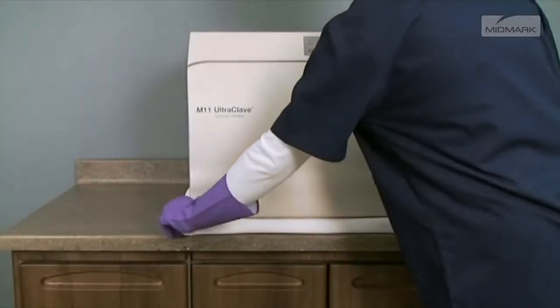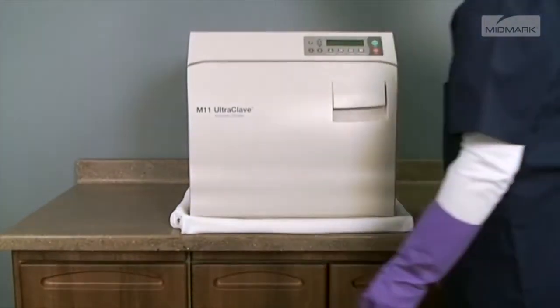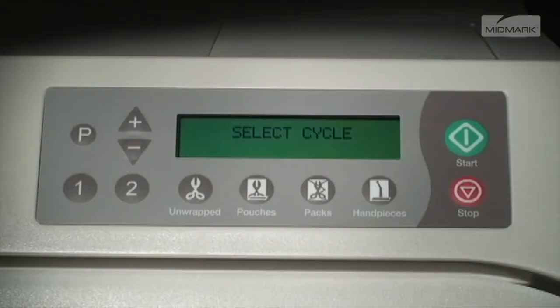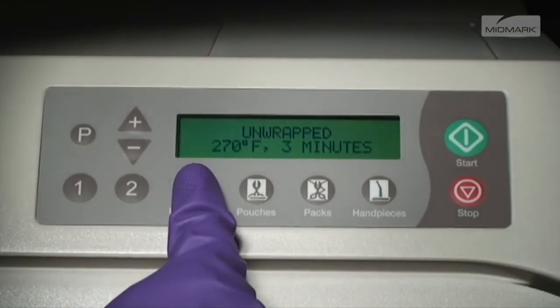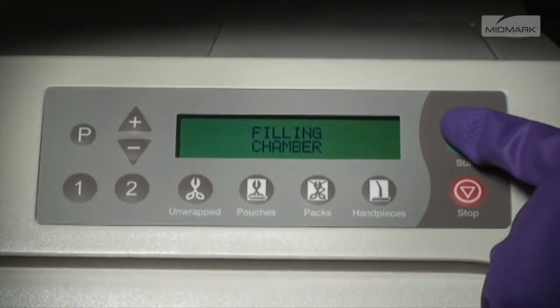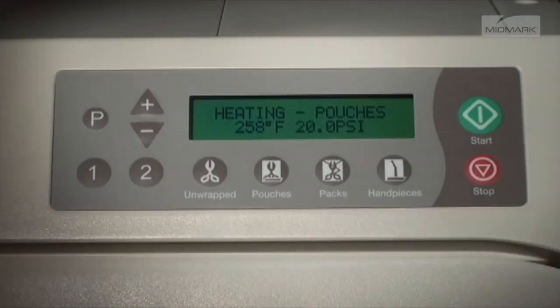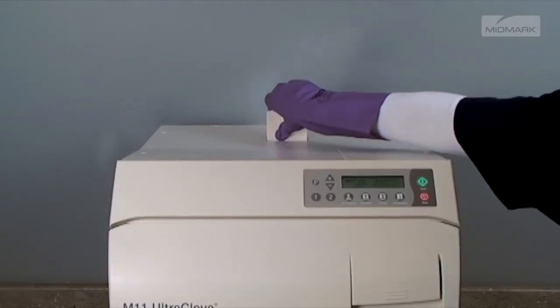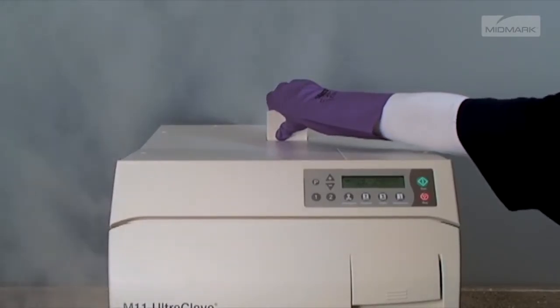Since high pressure and temperature steam will be vented from under the autoclave during this check, place a rolled towel around the bottom of the autoclave to act as a steam barrier. Press the unwrap cycle and then start. Monitor the display and wait for the pressure to reach 20 psi. When 20 psi is reached, pull upward firmly on the relief valve lever on top of the autoclave cabinet and hold it open for 3 seconds.